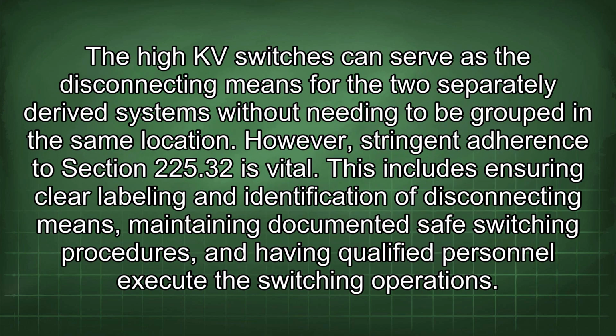The high kV switches can serve as the disconnecting means for the two separately derived systems without needing to be grouped in the same location. However, stringent adherence to Section 225.32 is vital. This includes ensuring clear labeling and identification of disconnecting means, maintaining documented safe switching procedures, and having qualified personnel execute the switching operations.